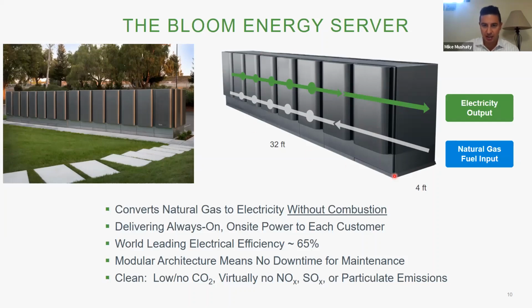The reason we call this a 250 kilowatt energy server is because the extra power module allows us to act and feel like the traditional legacy critical infrastructure systems that you're probably accustomed to currently serving your critical operations on campus. This level of redundancy gives us a level of fault tolerance in case we have an issue with an individual power module. It does not disrupt the fully rated amount of power being delivered to your facility. It also allows us to do concurrent maintenance. We are going to turn the system on. It is going to produce power 24/7, 365, and we are not going to turn it off for the full 20-year life of the system. We can do all of the maintenance associated with the system without ever disrupting the fully rated amount of power to your facility. I can literally replace every single one of those fuel cell tiles in the system without ever disrupting the fully rated amount of power to the facility.